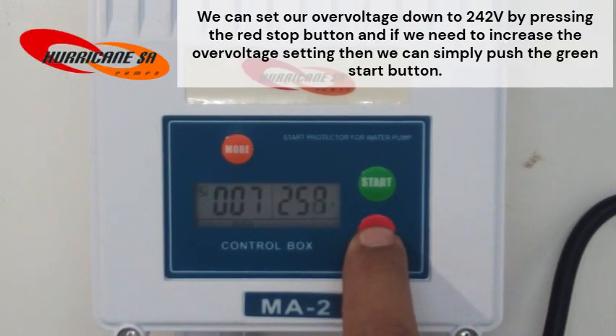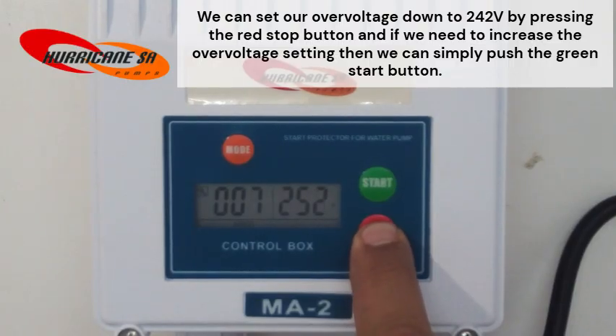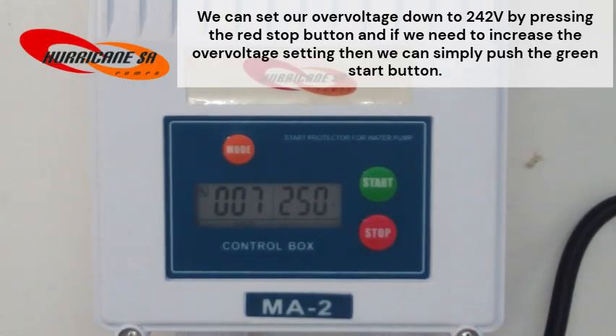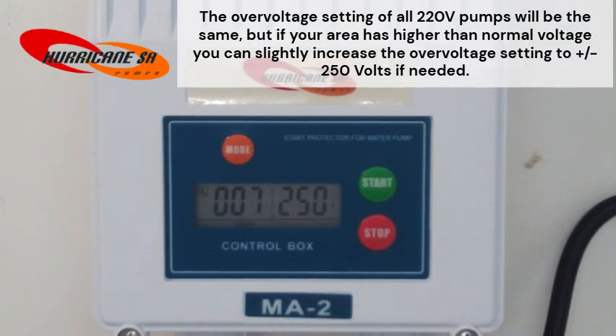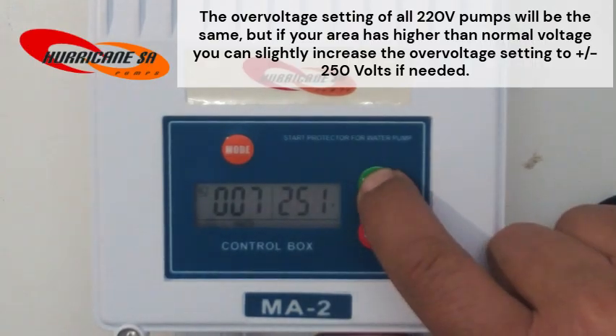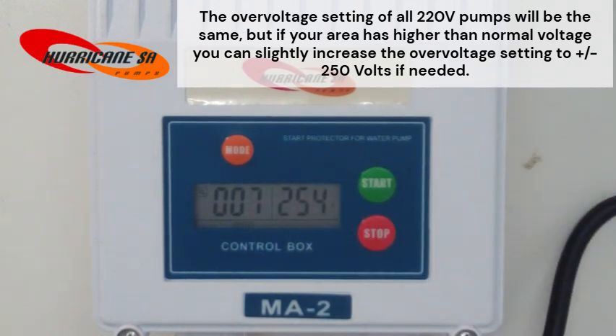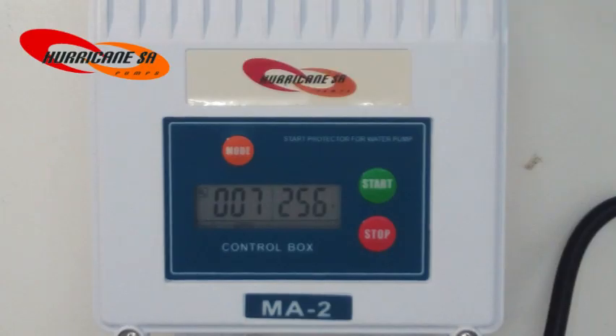We can set our overvoltage down to 242V by pressing the red stop button. And if we need to increase the overvoltage setting, then we can simply push the green start button. The overvoltage setting of all 220 volt pumps will be the same. But if your area has higher than normal voltage, you can slightly increase the overvoltage setting to around 250 to 255 volts if needed.